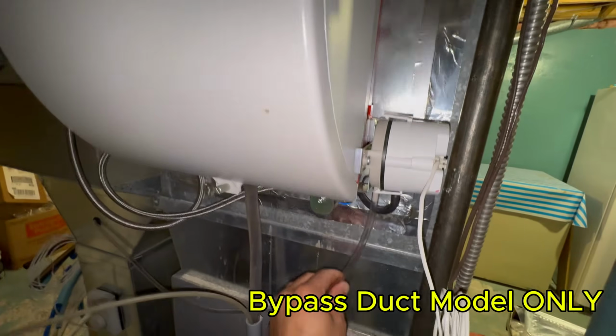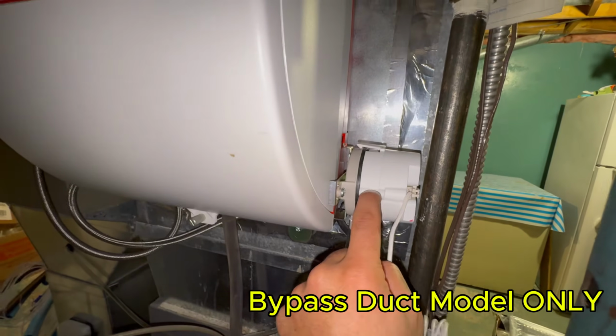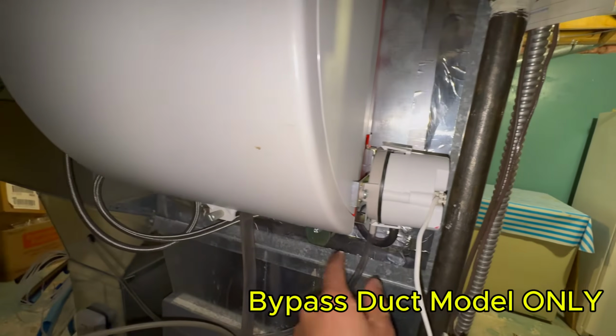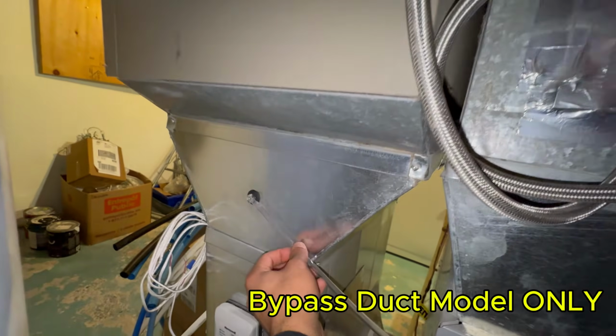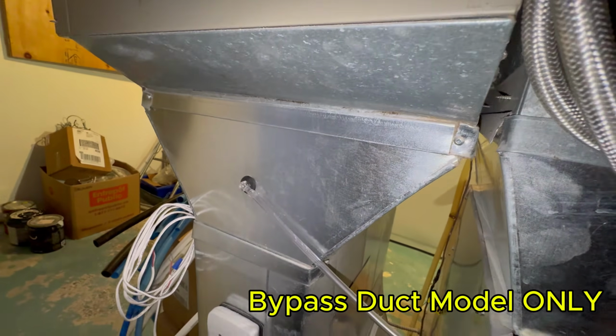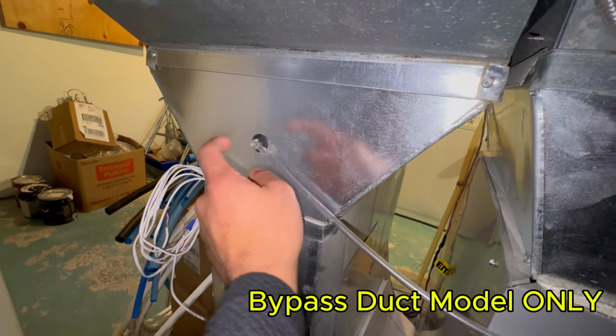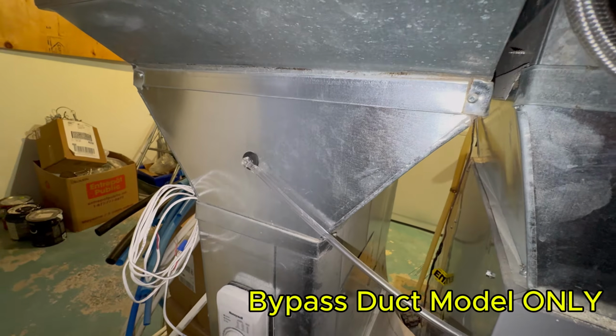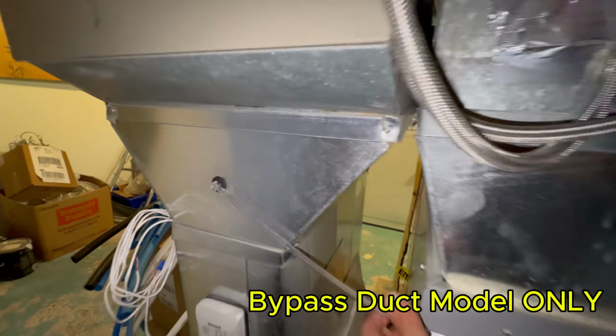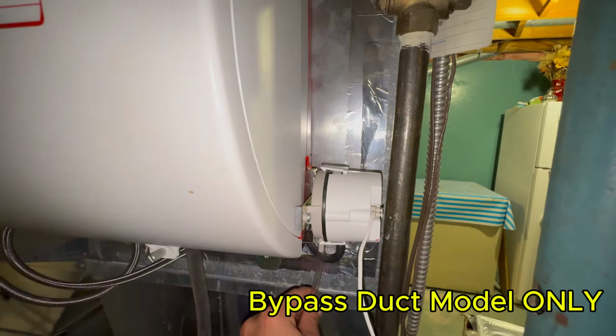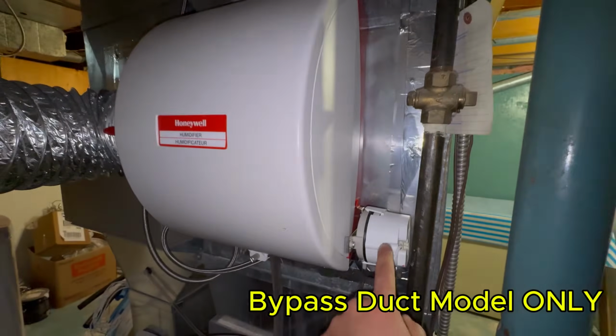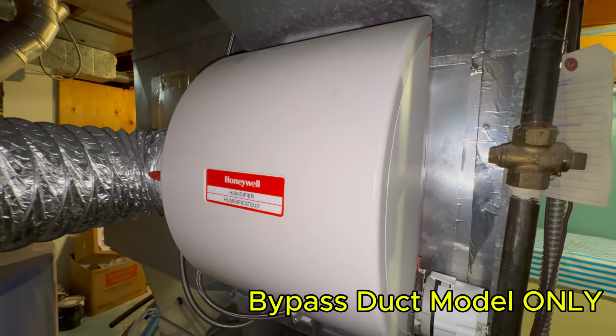You are using 1 piece of vinyl tubing to go from the solenoid and the pressure switch to the return side, which is the exact same installation in terms of the nipple that goes into the return side, and that 1 piece is going to trigger this to open and close, which then will allow this humidifier to run.